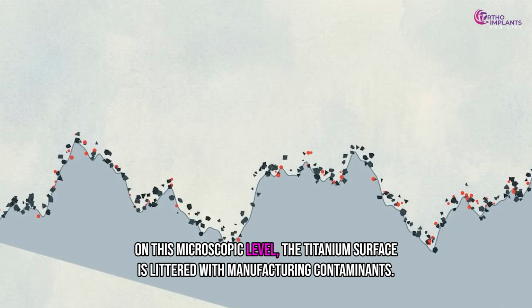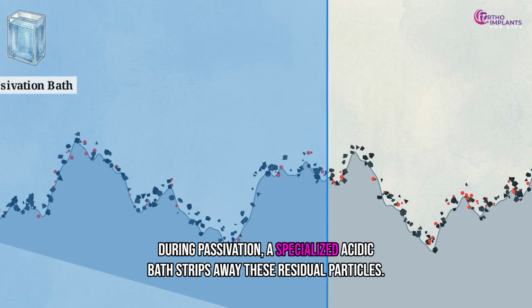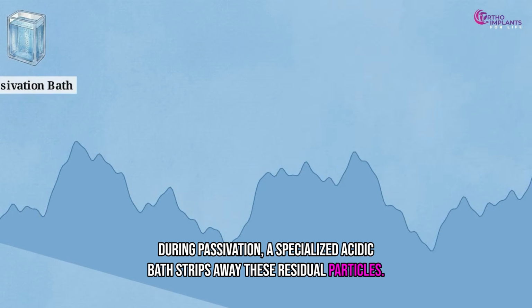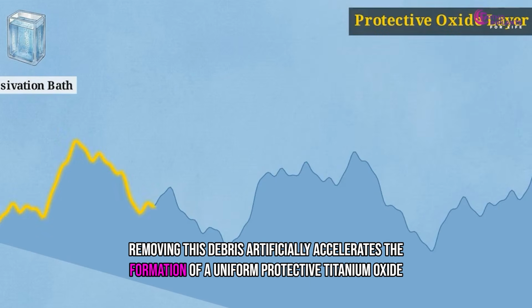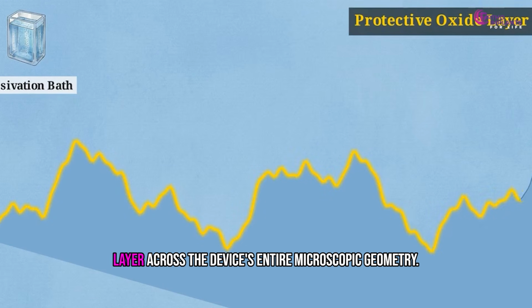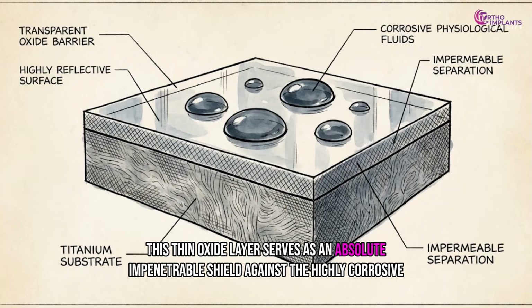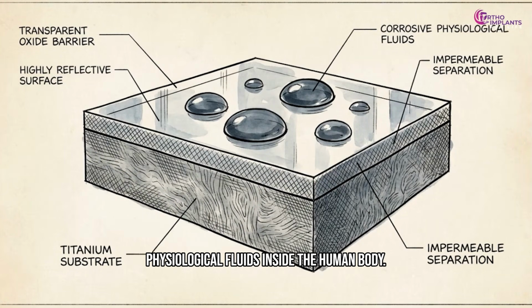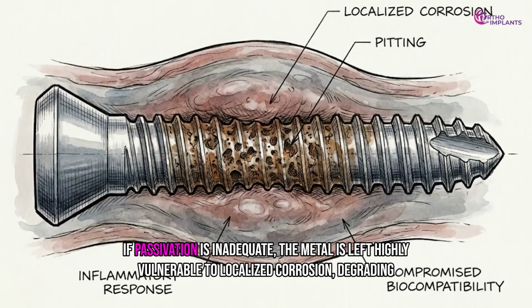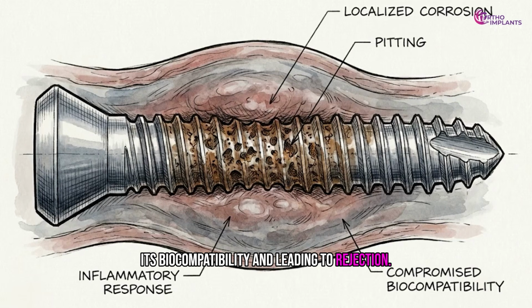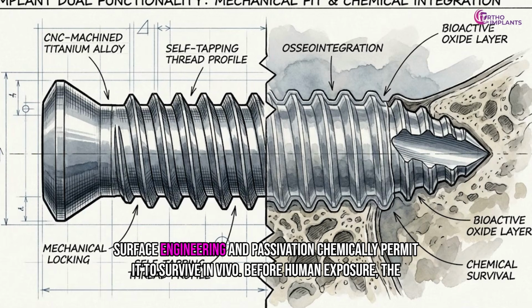On this microscopic level, the titanium surface is littered with manufacturing contaminants. During passivation, a specialized acidic bath strips away these residual particles. Removing this debris artificially accelerates the formation of a uniform, protective titanium oxide layer across the device's entire microscopic geometry. This thin oxide layer serves as an absolute, impenetrable shield against the highly corrosive physiological fluids inside the human body. If passivation is inadequate, the metal is left highly vulnerable to localized corrosion, degrading its biocompatibility and leading to rejection. Machining allows physical fit. Surface engineering and passivation chemically permit it to survive in vivo.